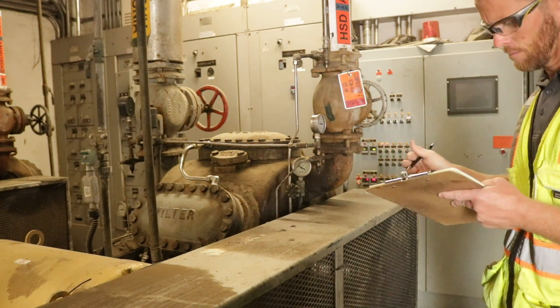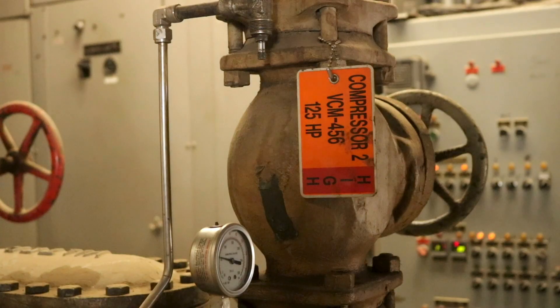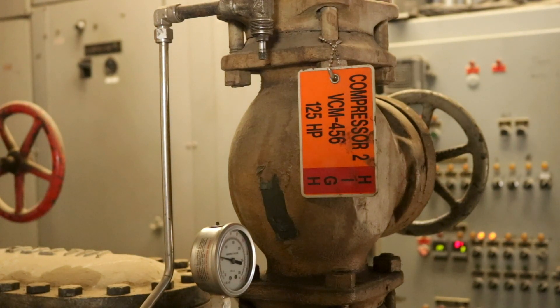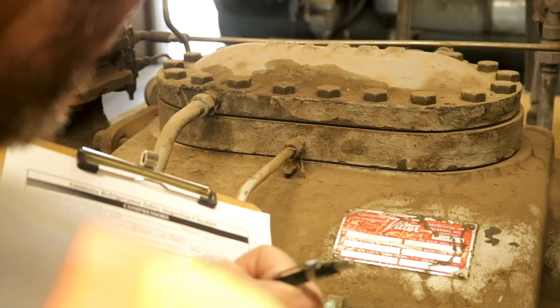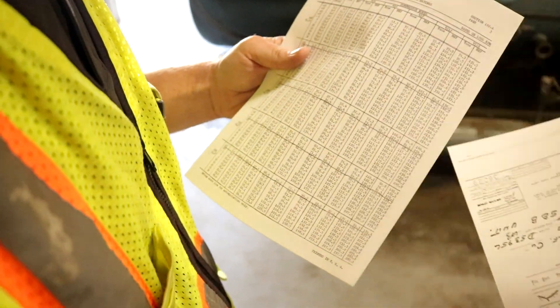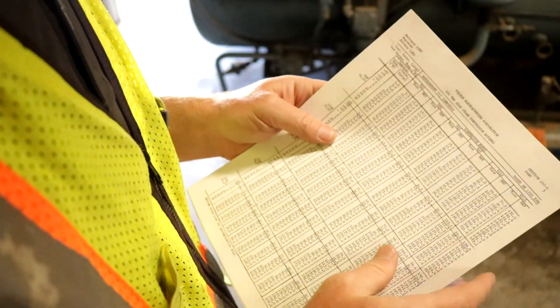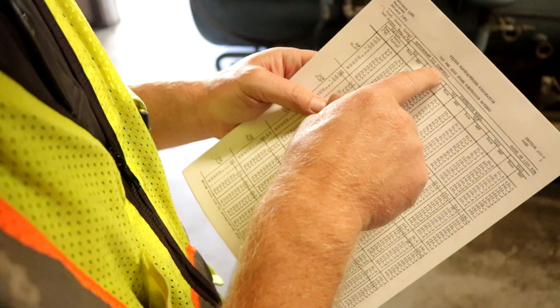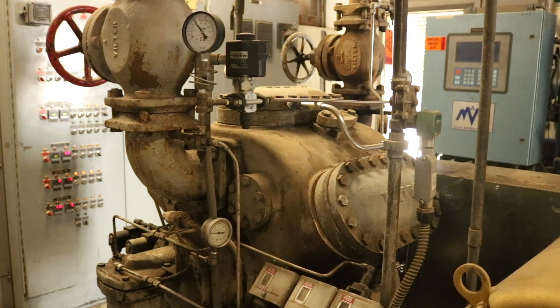Item A asks if the equipment is labeled and has a legible nameplate. A proper label consists of the component name and ID number. Items B and C ask if the compressor is suitable for ammonia and operating within limits. Suitability for ammonia can be verified by the equipment specifications provided by the manufacturer.